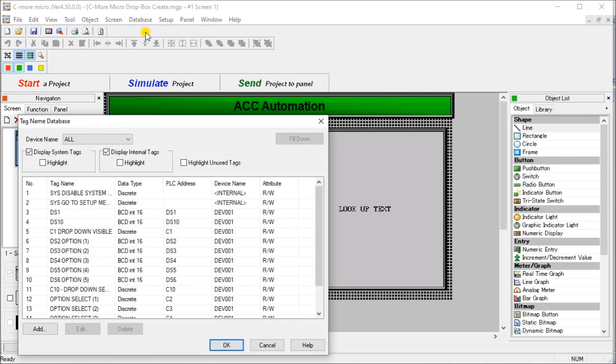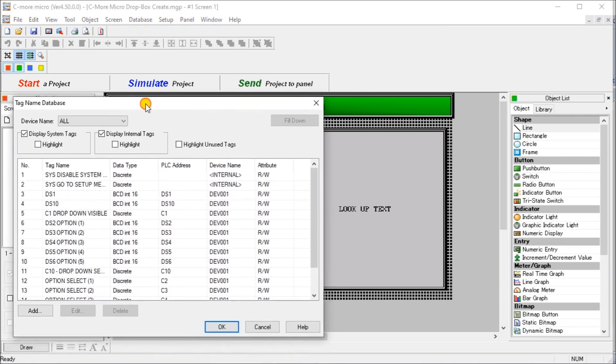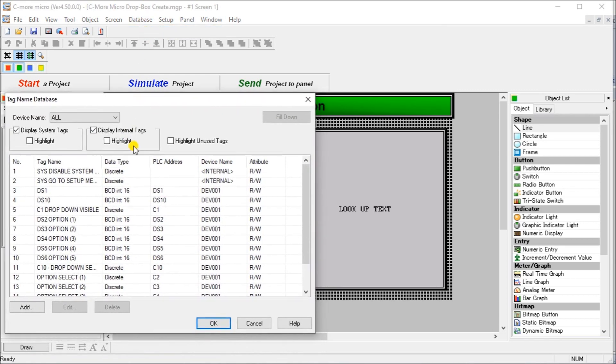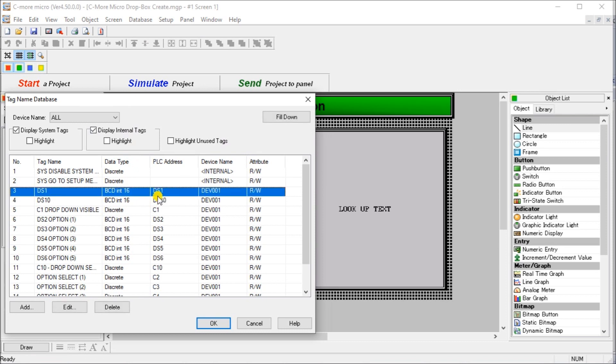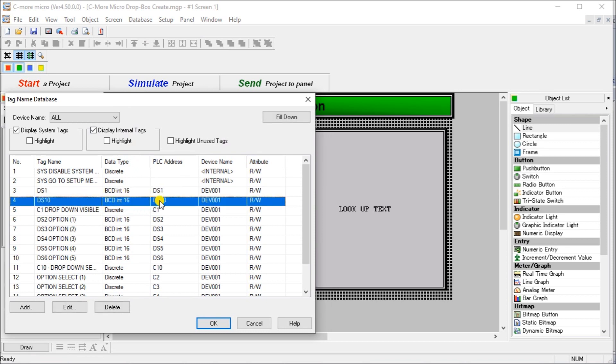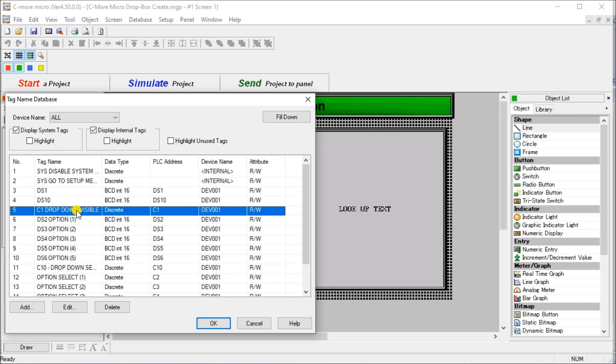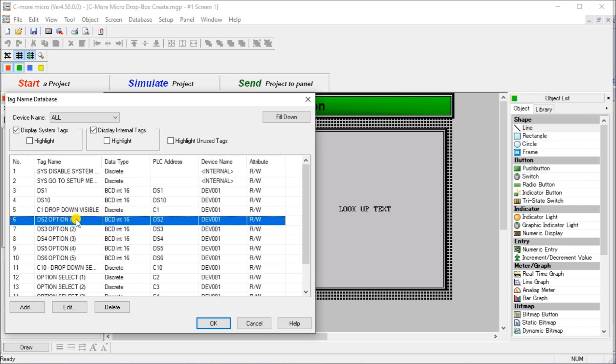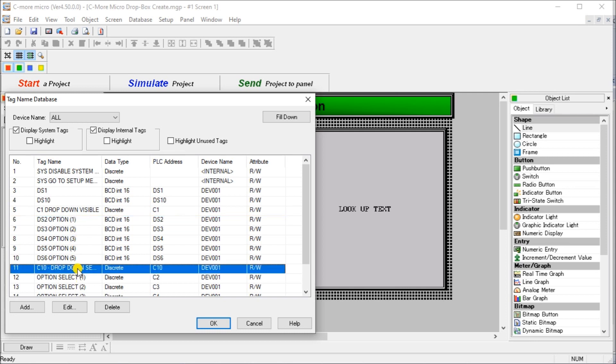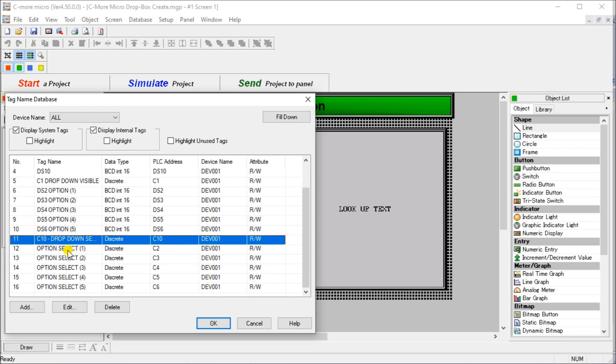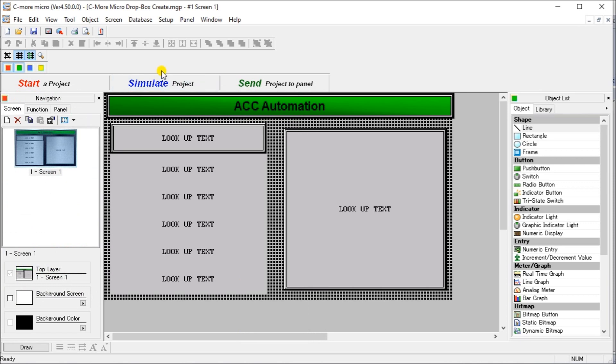And then what we'll look at is our database and our tag name database. So there's a few different parts to our drop down menu, and you'll see that we have DS1, which is our selected value. Then we have DS10, which is our answer value or lookup value. Then we have our C1 we're using for our visibility so we can hide other elements on our drop down. Then we have DS2, 3, 4, 5, and 6, which are the options that we have for our selection. Then we have C10, which is a drop down selection. And then we have a selected option. So this is like a push button that will have selection 1, 2, 3, 4, 5.